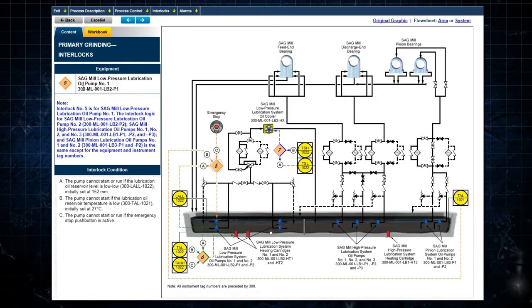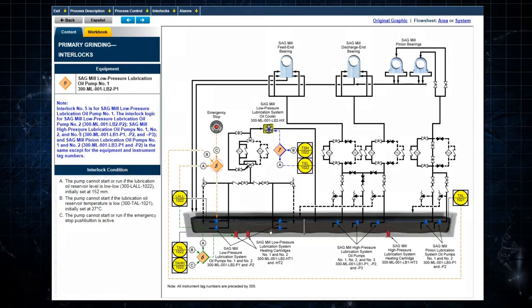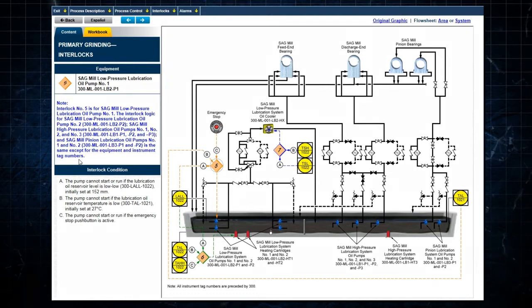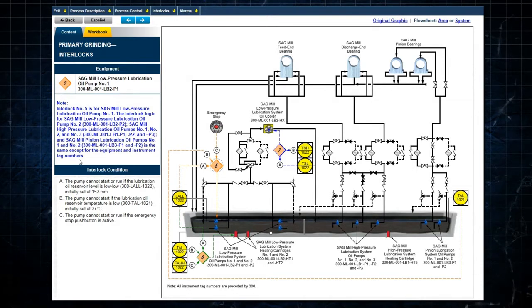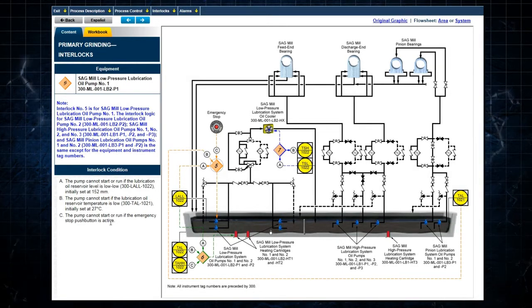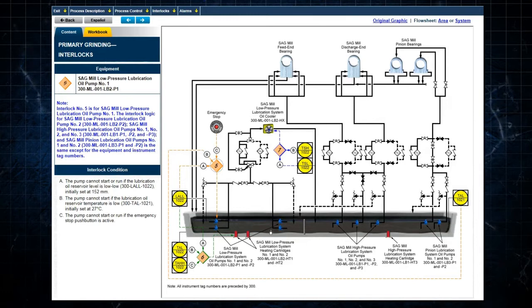Selecting an interlock diamond on the right calls up the interlock logic for a particular pump on the left. In this case, three logical inputs must be satisfied to allow the sag mill low pressure lubrication system oil pump to operate.